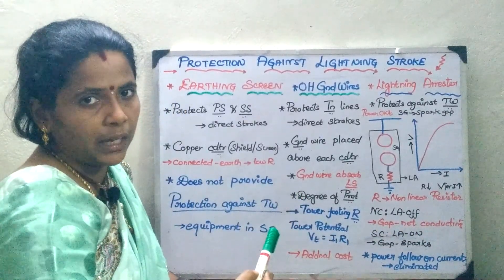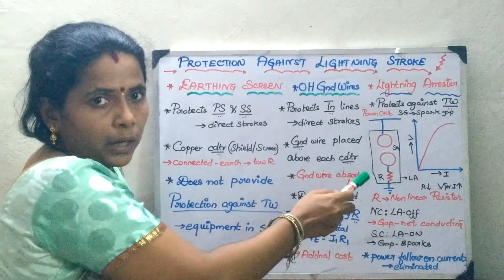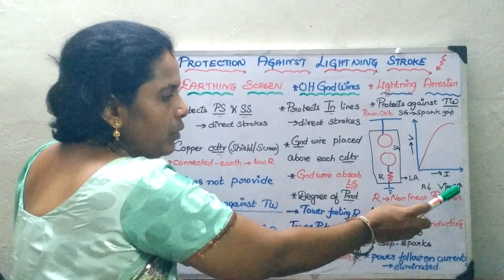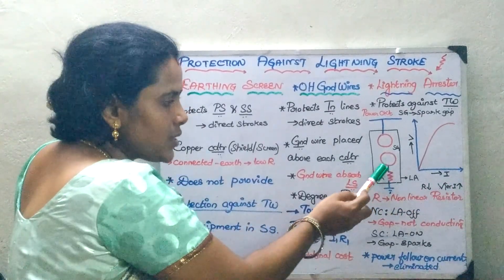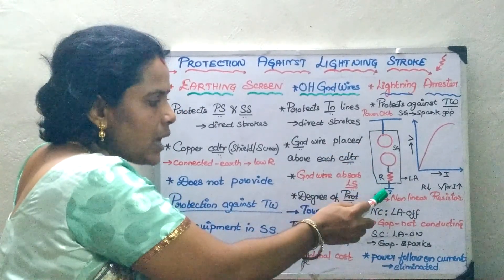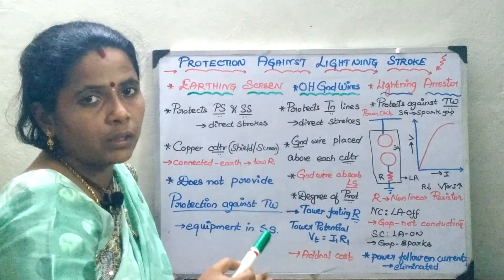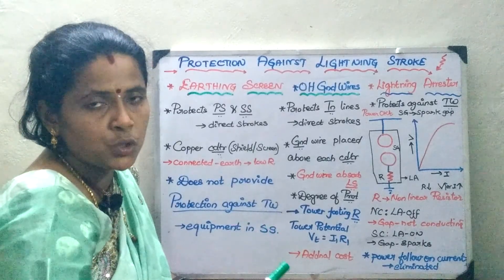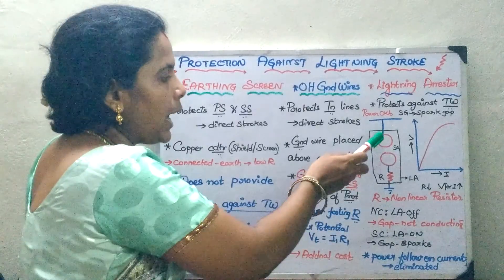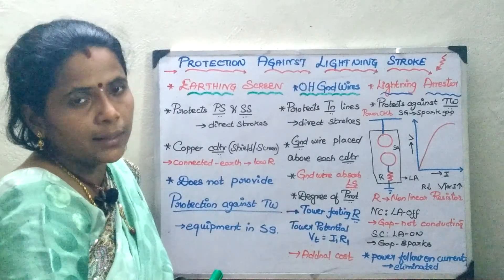Now consider a case where lightning falls. Whenever a lightning is going to fall, you are going to have a very high voltage. In that case this resistor is going to act as a short-circuit path and it is going to drain this high surge to the ground. Whenever you have a high voltage, it should be discharged to the ground through a low resistance path, which is facilitated by arcing over your spark gap and the current is drained via this non-linear resistor.